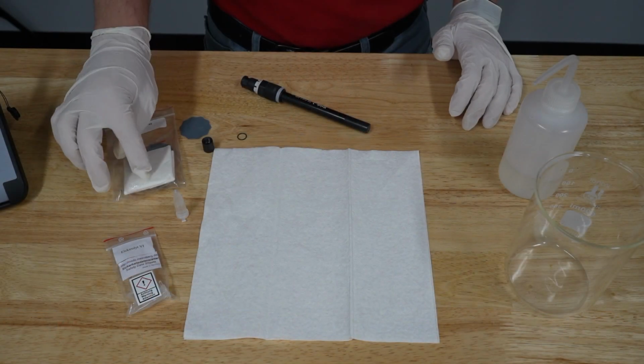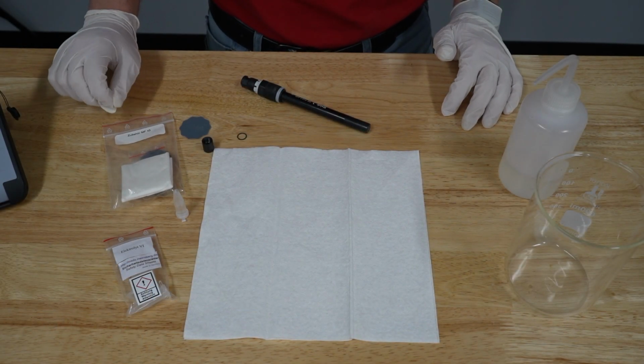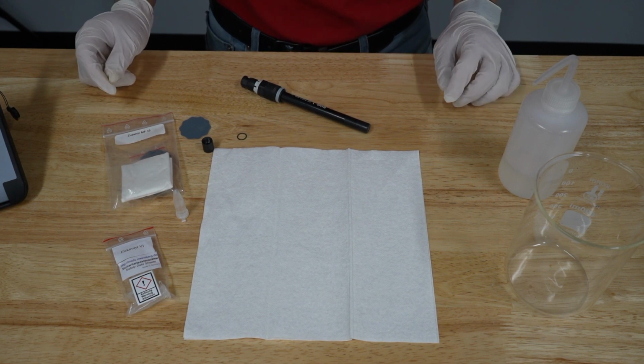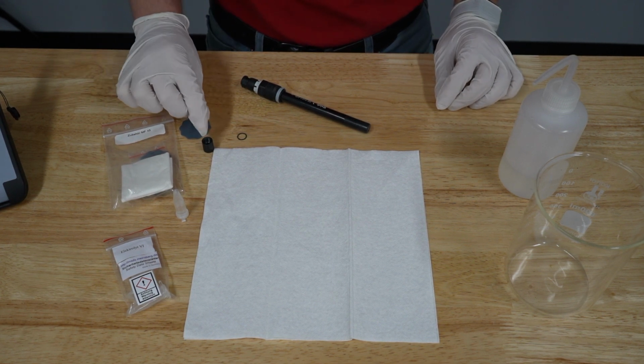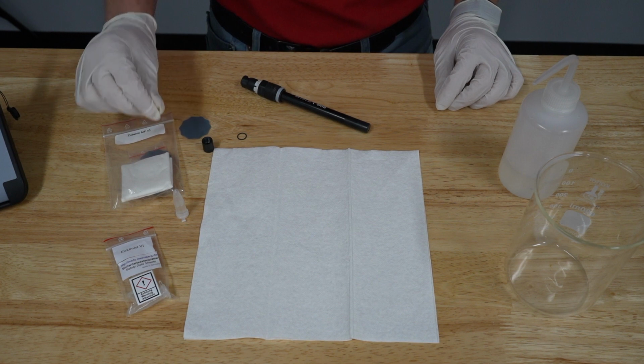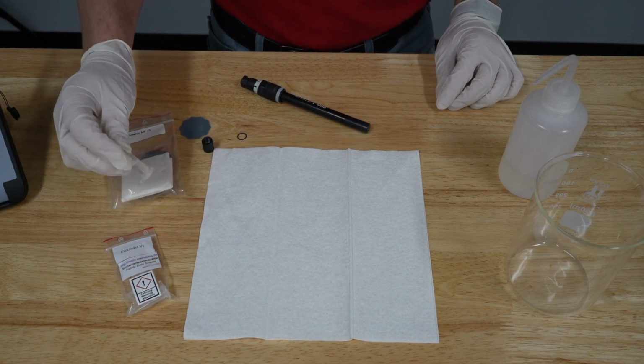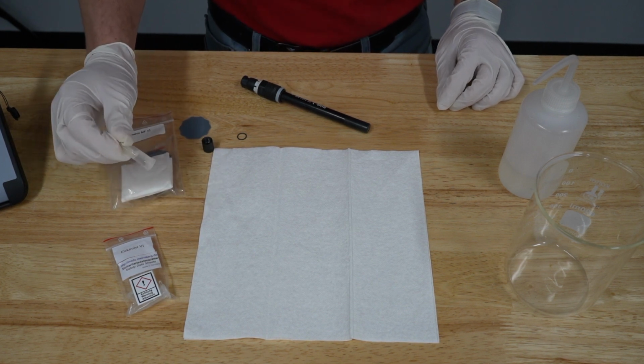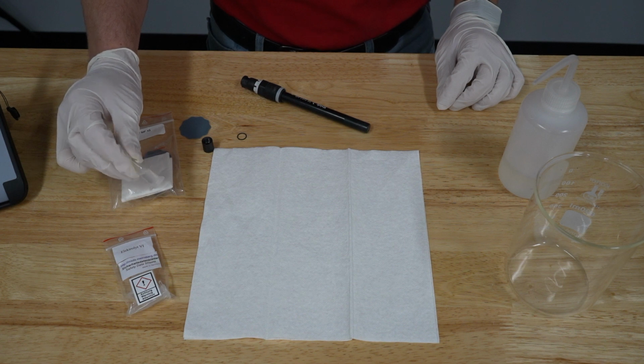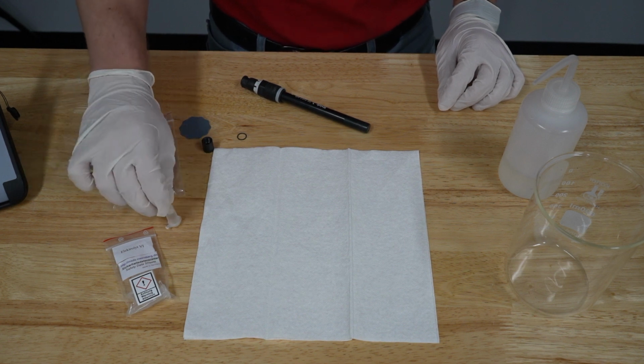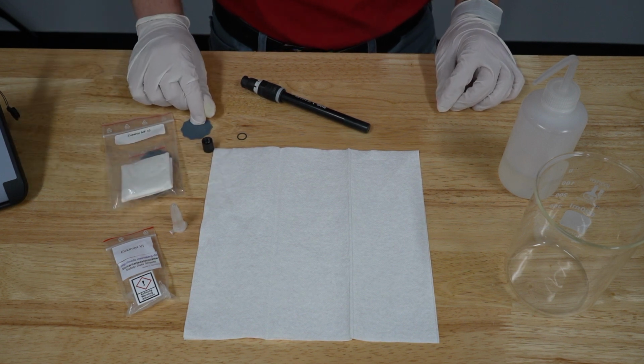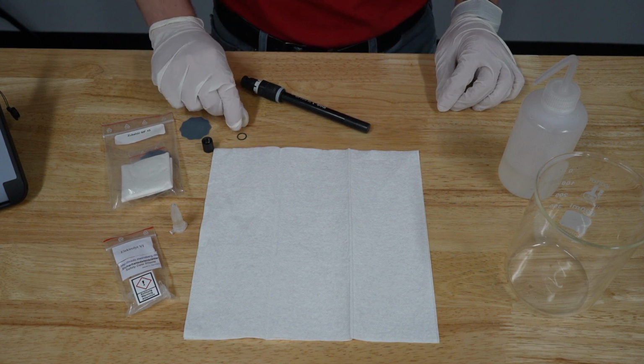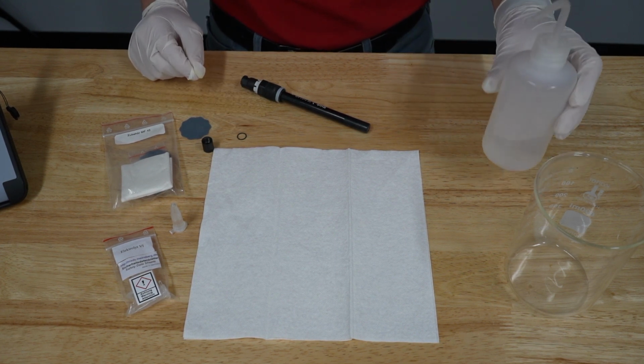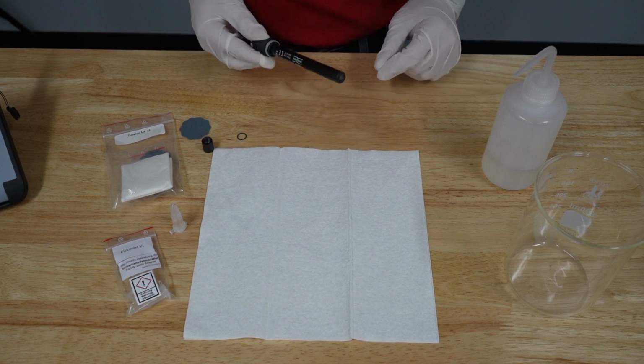We'll use the equipment that came with your SE715 sensor: the membrane replacement cap, electrolyte solution, which can be about 13 pH, so I'll be wearing gloves to avoid hand irritation. We also have a sandpaper patch, an O-ring if needed, and some DI water to rinse the sensor off.